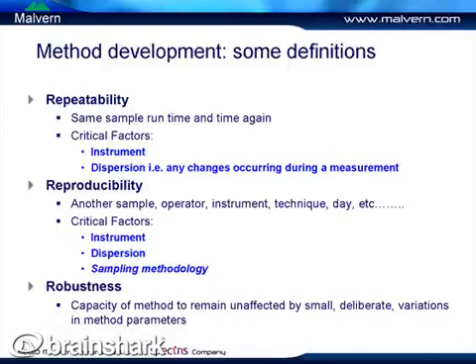Finally, we're looking at robustness, which involves deliberately altering the method parameters — making small changes to your method to test whether small variations have any effect on the result. So you're testing how sensitive the method is to slight variations.